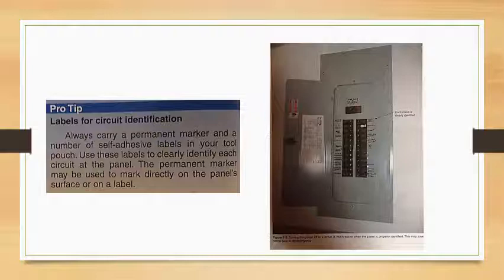Work and clearances. To ensure accessibility and maintain service or operate electrical equipment, the NEC insists the work clearances shall not be less than 30 inches wide in front of the equipment. Further, these clearances must not be cluttered with any items, including crates or boxes or in any way used for storage. Storing items in front of electrical equipment would prevent rapid access in the case of an emergency. See figure 7-1.